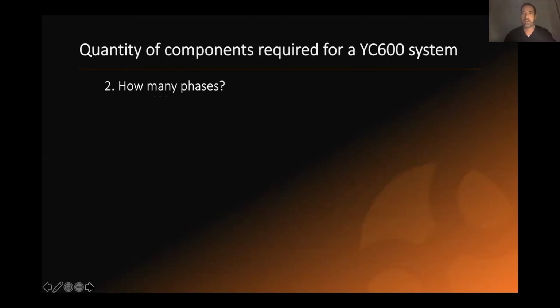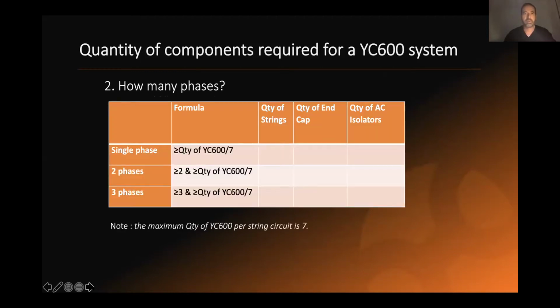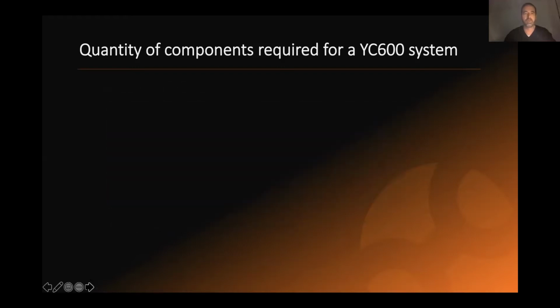All right, already - how many phases? So you can only put 7 micros, YC600, on a single branch. It's a current limitation for the breaker. You can only put 3 QS1 on a single branch - also a current limitation. These kinds of things you can read on the data sheet.